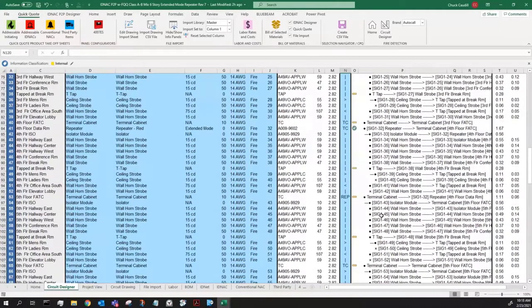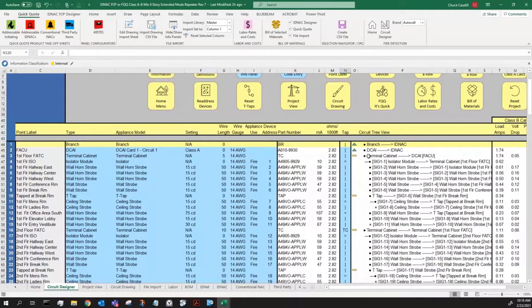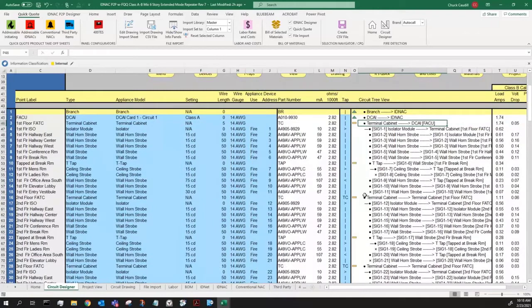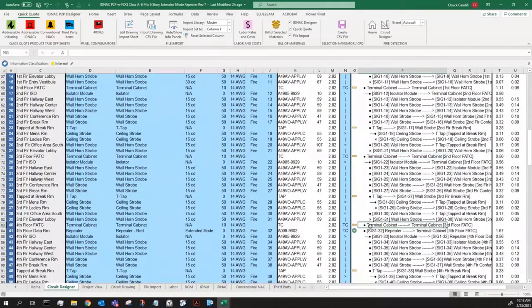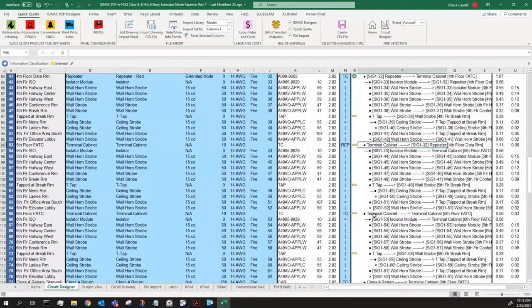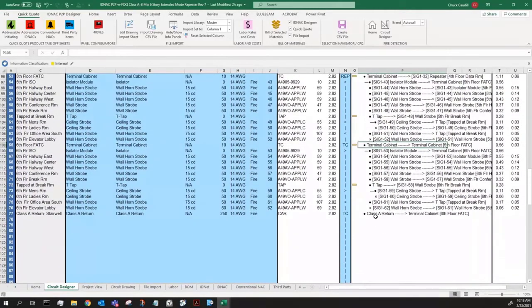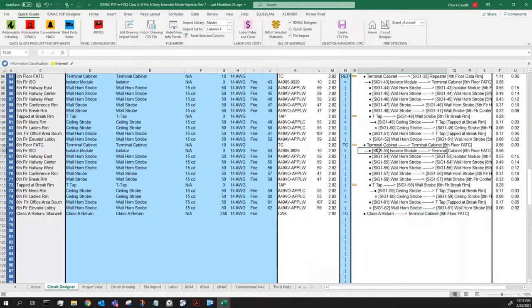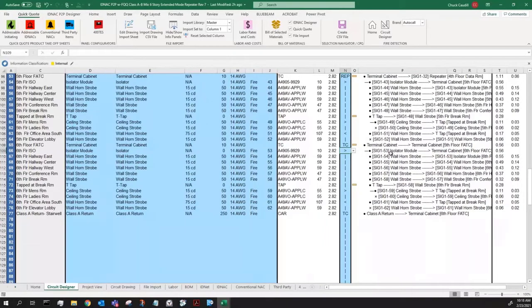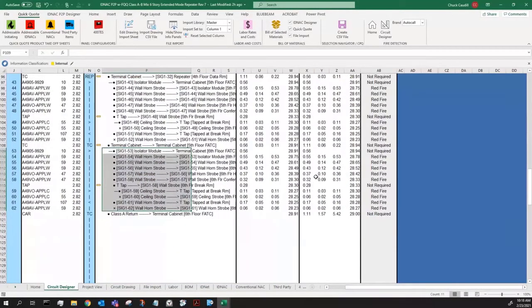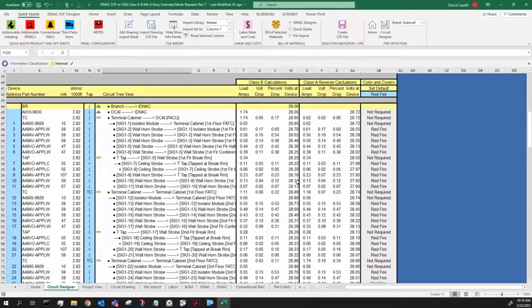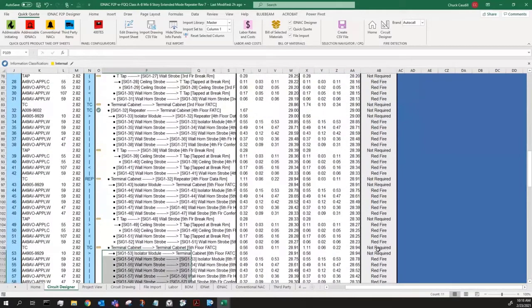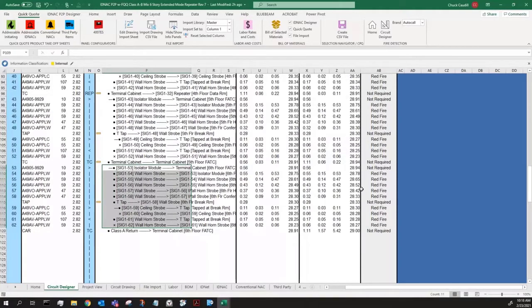So this line over here, far left before we do any tapping out, DCAI to terminal cabinet one, to terminal cabinet two, terminal cabinet three, to four, repeater in series and extended mode, to the fifth floor terminal cabinet, to the sixth floor terminal cabinet, to the Class A return. My field wiring is done just like we did on previous pages. We started with an ISO module. We tapped it out. So it's a tap off of that terminal cabinet. All the field wiring devices are there. When I come over to look at the voltages, we start at 29 volts from the top, we work our way down. Same thing over on this side, 29 volts on the other side, down the first floor, working our way. It goes up to the top and works its way down from the top down.